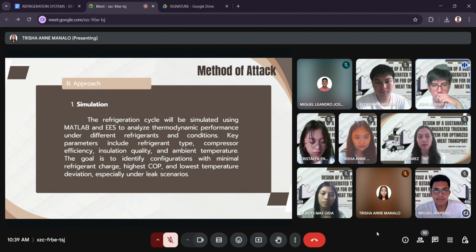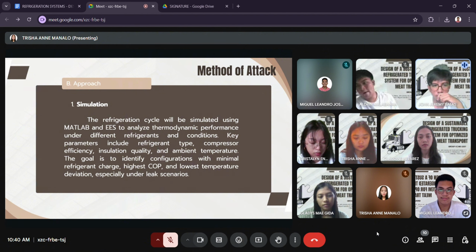Next, our approach combines simulation and experimental validation using MATLAB and Engineering Equation Solver (EES). We simulated the refrigeration cycle under different refrigerants and varying conditions. We examined how different compressor efficiencies, insulation quality, and ambient temperatures would affect overall performance. These simulations help us identify system configurations that required the least refrigerant charge, offered the highest COP, and showed the lowest temperature fluctuations even under potential leak scenarios.